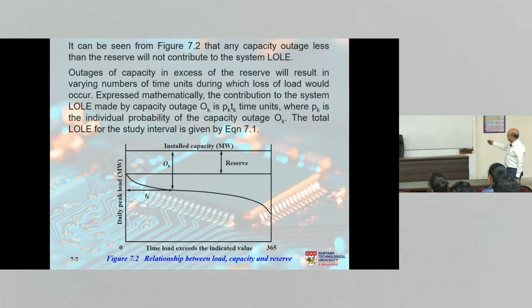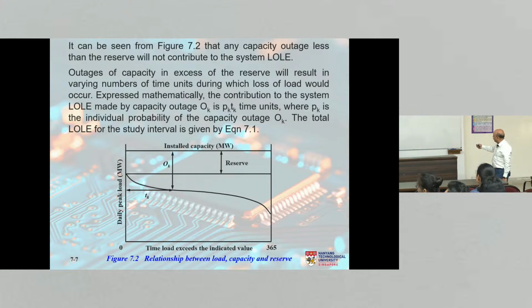From this figure, you notice that this is the daily peak load variation curve over 365 days, for example. And this is the installed capacity in megawatt. This is the reserve in the system, because anything greater than the peak load is obviously the reserve in the system. And suppose there is an outage O subscript K. O stands for capacity outage. And K means it could be outage 1, outage 2, outage 3, where K goes from 1 to whatever. How many states are there in the capacity model? That's what K goes up to, yeah?